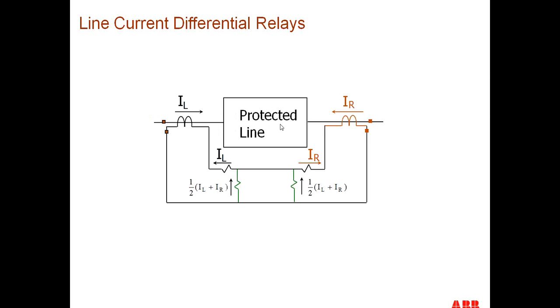So we can see the same sort of circuit, though. We have a protected line. We have the current transformers at either end of the protected line. We have a relay at each end of the protected line, and we have this communications path between the 2 relays that we need to worry about. And we still do the same comparison of the local with the remote signals at each end of the line. We develop an operate current and differential current based on the relationship between the restraint, the local and remote terminal currents.